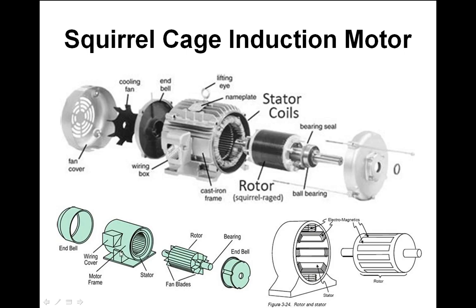There are no contacts, no centrifugal switch — nothing at all. The rotor spins purely by induction. This motor is called an asynchronous motor. The beauty is there are no sparks, no arcs, very little maintenance, no slip rings, no carbon brushes that wear down. The only wear and tear is the bearings — if well greased, they last a very long time. It's almost indestructible.